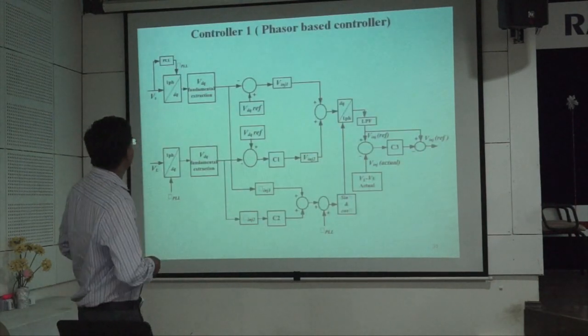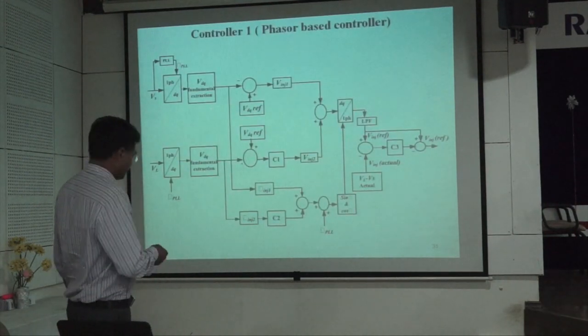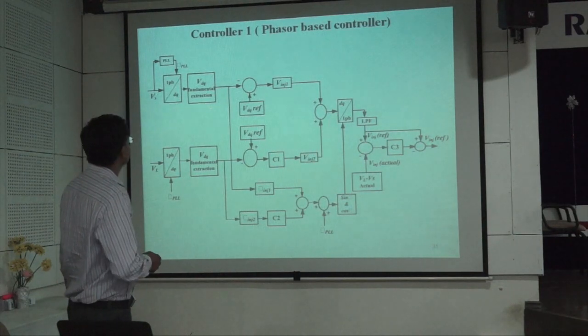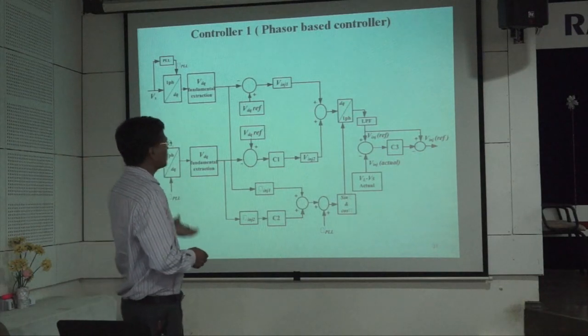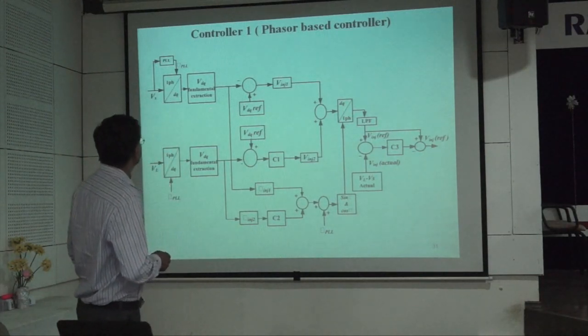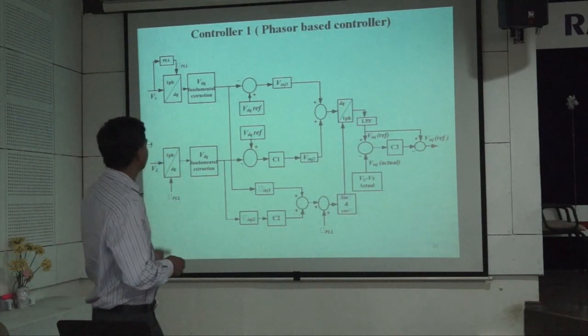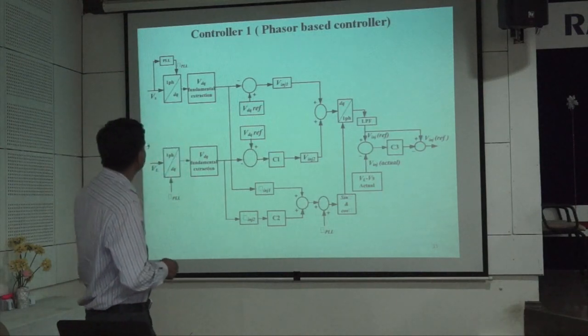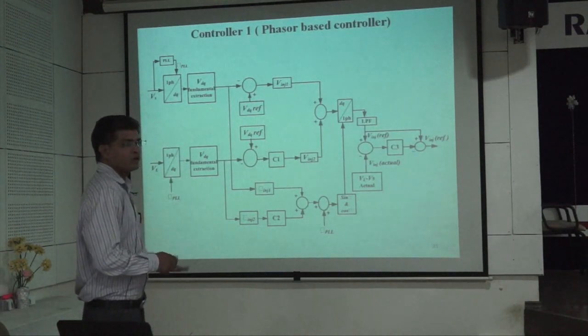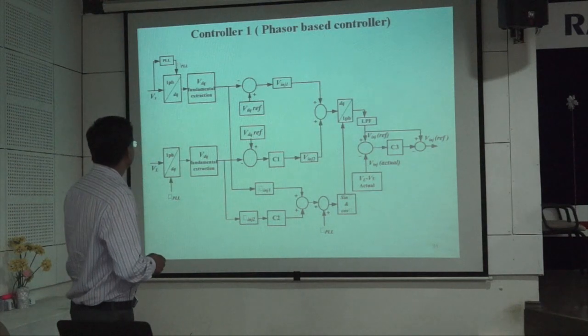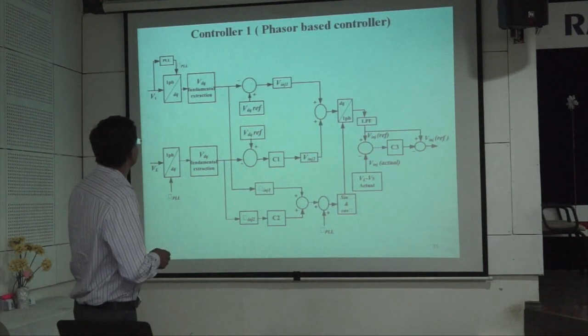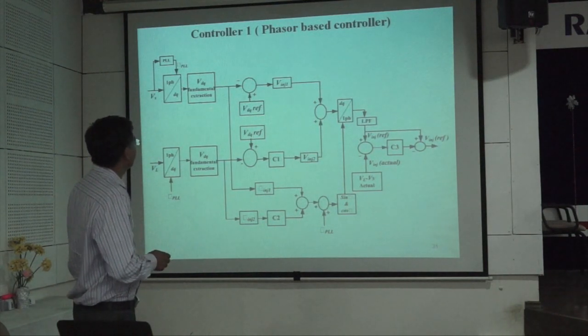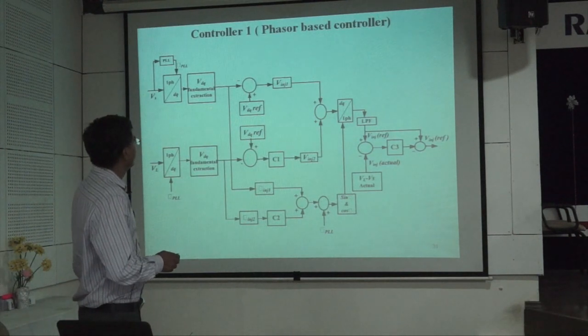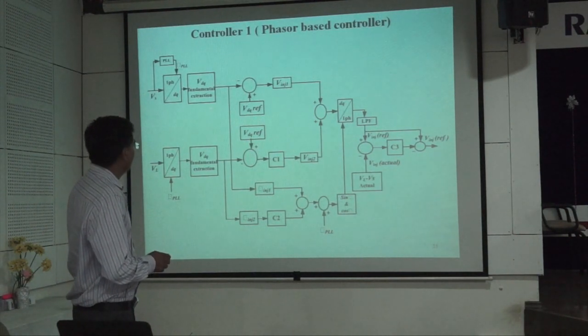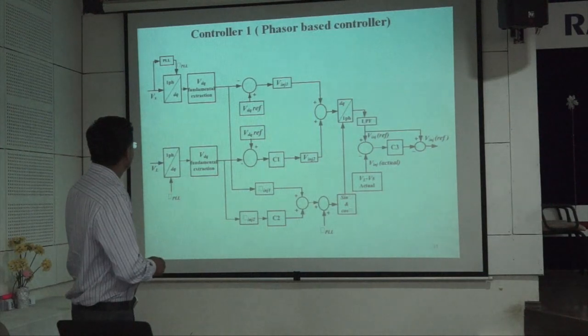And this is the controller. I have designed the controller on the phasor analysis, with single phase to ABC transformation. There are two controllers. The inner controller is for the transient analysis, and the second is for the improvement of the steady state error. So here fundamental components have been derived. It is compared with the reference value, the injected voltage. This is the closed loop.